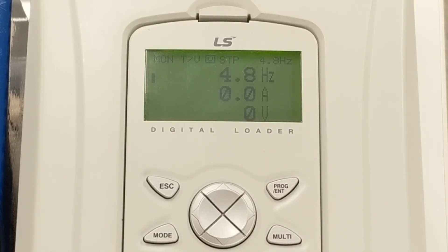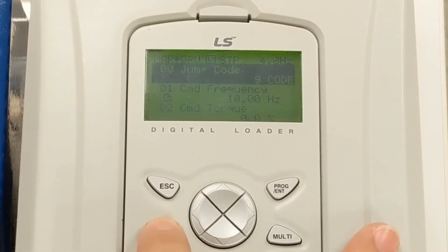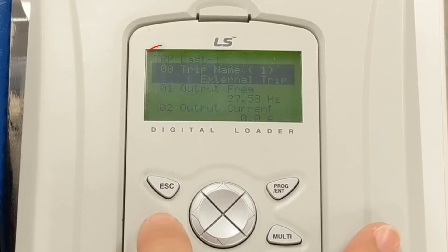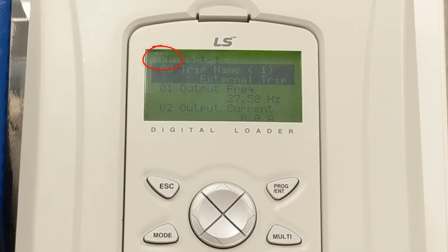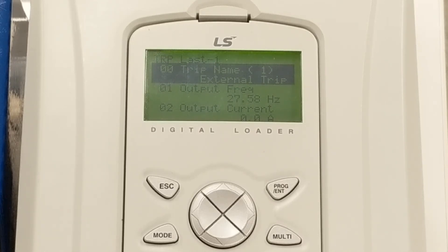There are a couple of other keypad modes you may find useful. Press mode a couple of times to go past the parameter mode and into the trip mode, designated TRP in the top left. Here you can see the five most recent trips that the VFD has recorded. This mode is an excellent tool for troubleshooting. If you do not have a trip mode, this simply means that the VFD has never tripped out or all previous trips have been cleared.